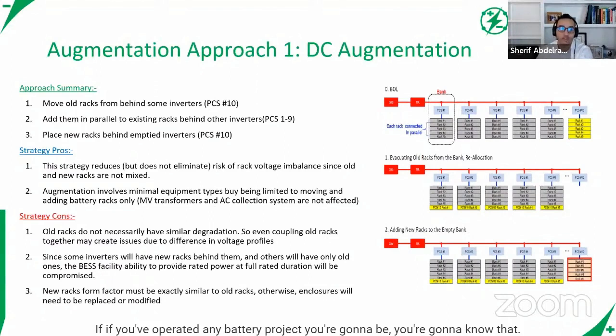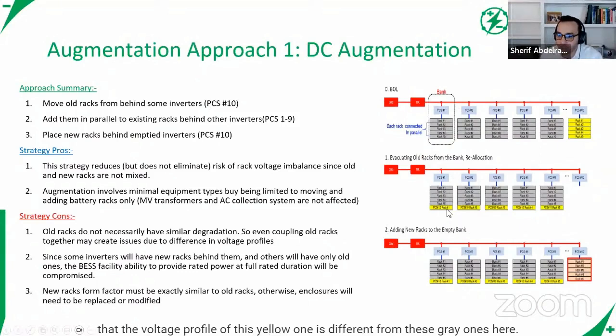If you've operated any battery project, you know not all inverters are online 100% of the time. You'll have one inverter go offline for a couple of weeks, maybe months, until you get that IGBT from the OEM and it gets fixed, meanwhile all the other inverters are operating. So it's more realistic to assume varying levels of degradation and accordingly varying voltage profiles across them. So when you take racks that have been treated the same way behind a single inverter and disperse them in parallel with others, there's a very probable case that the voltage profile of one rack differs from the others.